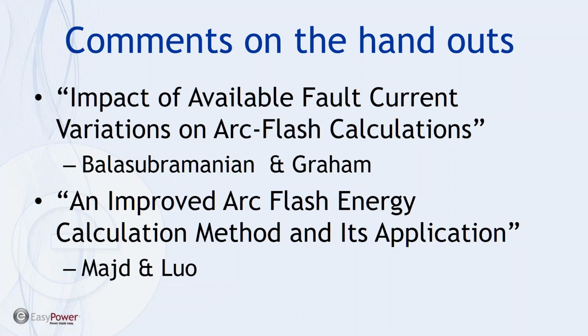The second handout is a paper that was presented by two EasyPower engineers at an IEEE committee session. It discusses the arc flash incident energy calculations and ways to make them less conservative in terms of the current being used in the calculations. Both of these we're going to touch on briefly, but I make those papers available as reference material. In fact, this whole presentation is more of a reference as far as your utilization of the tools, and these are not necessarily recommendations for any project specifically.